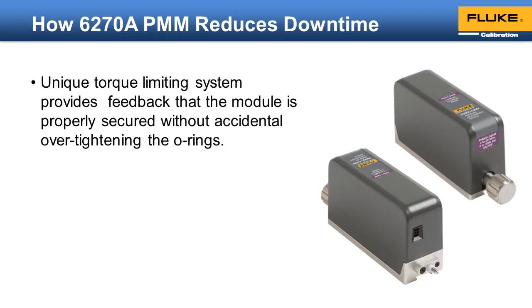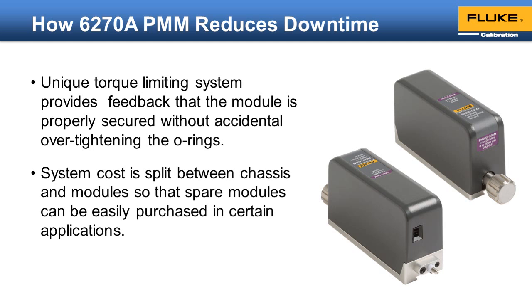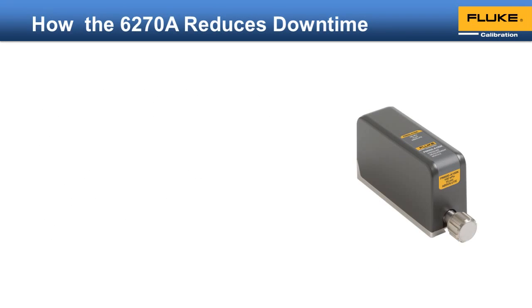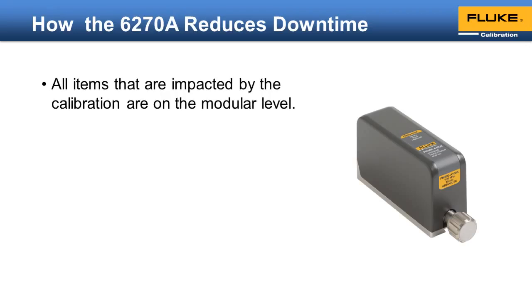On systems without this feature, it's easy to damage O-rings by over-tightening and extruding the O-rings. In addition, the system cost is split between the chassis and modules so that you can easily purchase spare modules to swap into the system, while the originals are sent in for calibration. Great care has been taken to ensure that all items that are impacted by the calibration are on the modular level. The measurement module includes the actual pressure sensing element, the electronics that read the output of the sensing element, and the coefficients that are applied to that output to calculate the final pressure value.